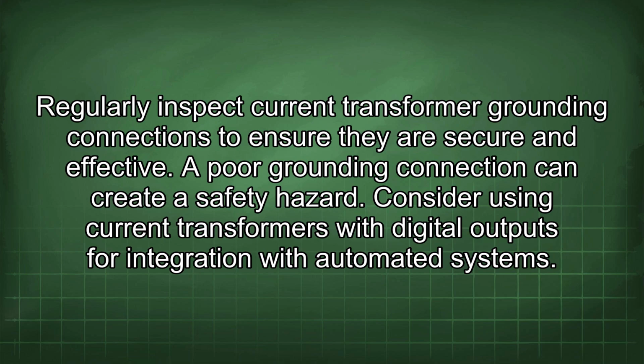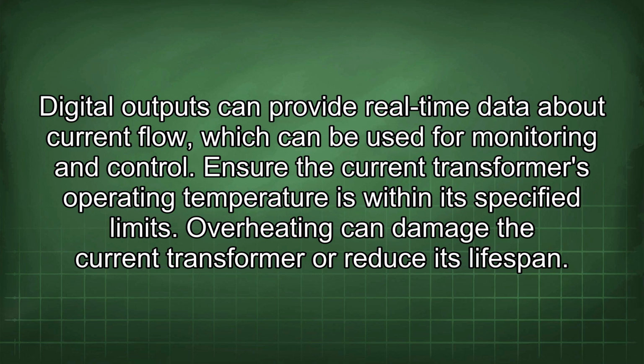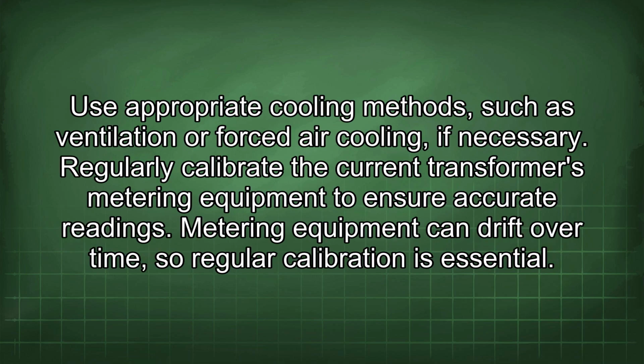Consider using current transformers with digital outputs for integration with automated systems. Digital outputs can provide real-time data about current flow, which can be used for monitoring and control. Ensure the current transformer's operating temperature is within its specified limits. Overheating can damage the current transformer or reduce its lifespan. Use appropriate cooling methods such as ventilation or forced air cooling if necessary.